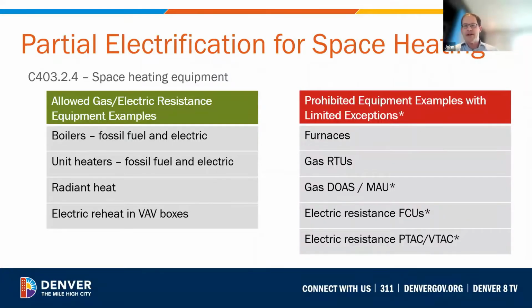Dedicated outside air systems are an excellent choice for conditioning ventilation air, especially when coupled with zonal systems for heating and cooling that can cycle on and off with the load. It limits the use of outside air to where it's needed, and those DOAS systems can often use energy recovery to limit the heating requirements further. Some fossil fuel systems may be able to comply with the performance pathway if they meet the specified requirements. Refer to the commercial performance training for details.